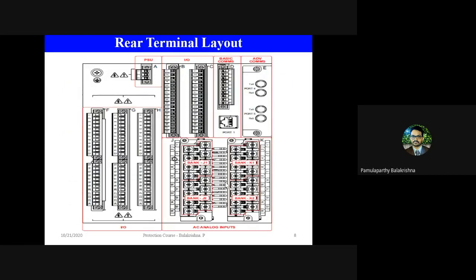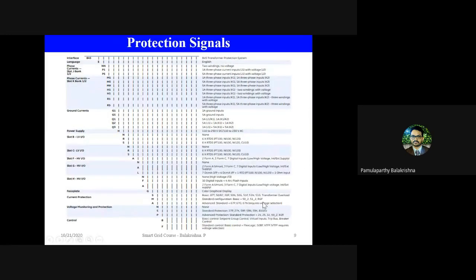What I mentioned is about the flexibility in hardware design. It also has flexibility in terms of application support or protection function support. As I said, different kinds of signals are required to execute different types of protection. This digital relay can take any form of signal. For example, the secondary side of a CT can be either 1 ampere or 5 ampere. You can connect anything. Similarly, ground CT. Power supply can be AC or DC. Different designs of temperature sensors can be connected, different designs of digital input and digital output relays can be connected, and different types of transducers which give signals can be connected.